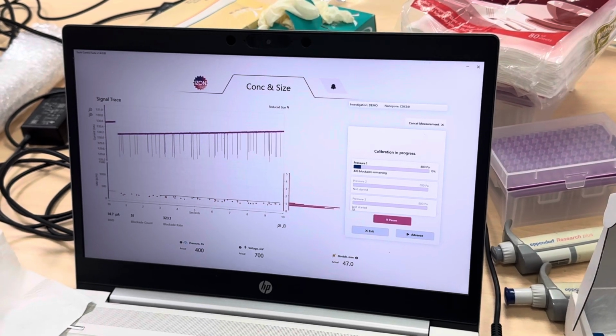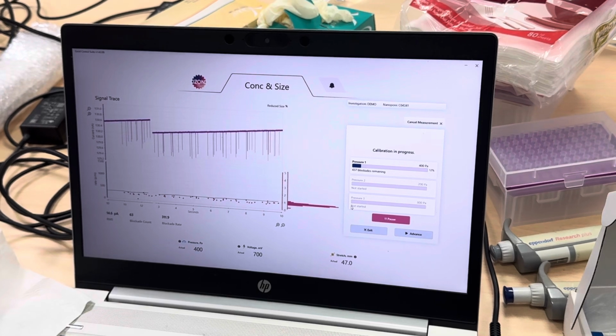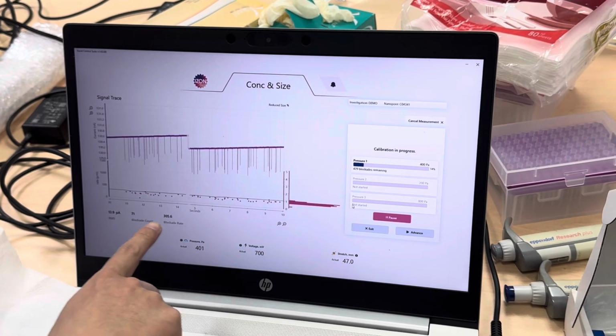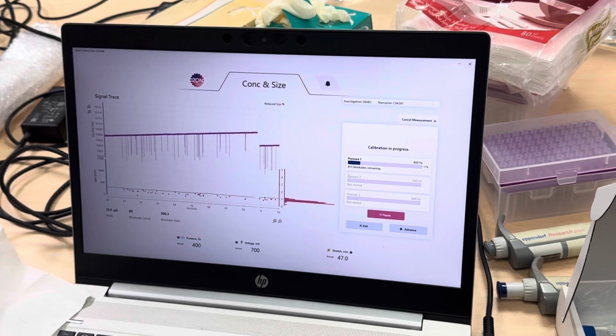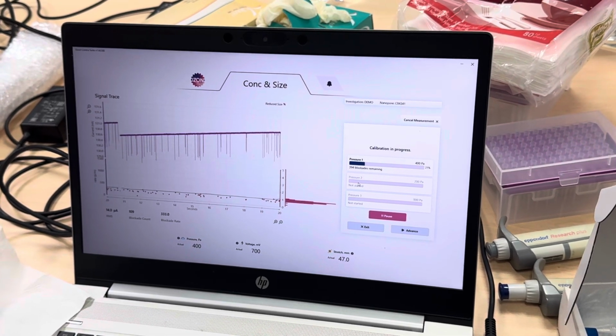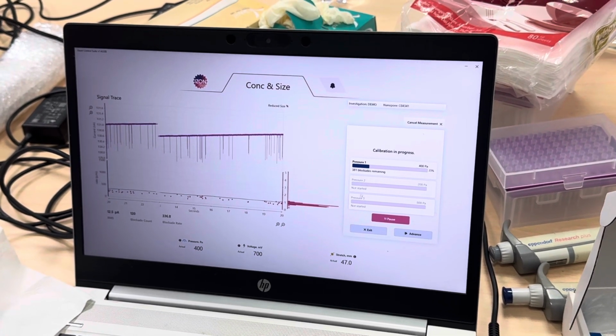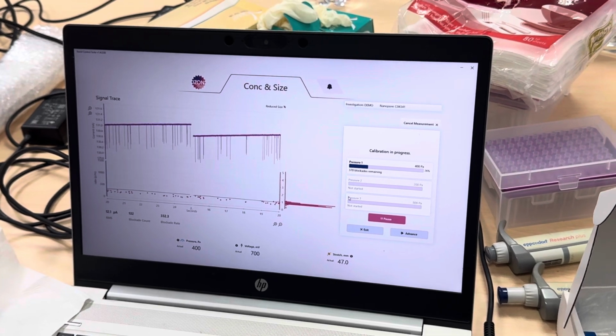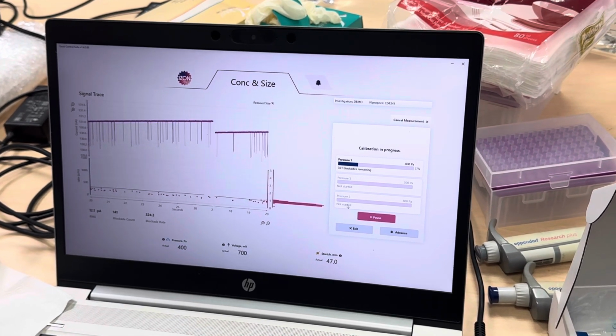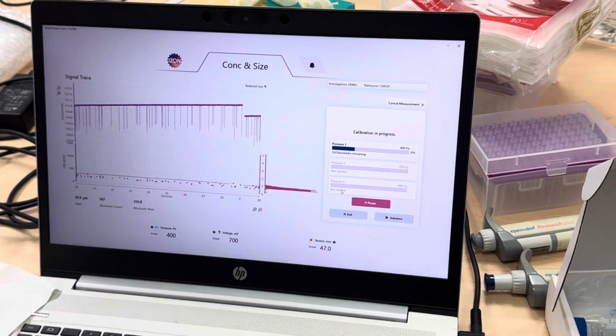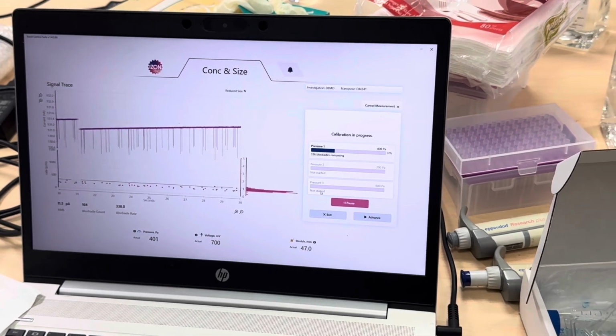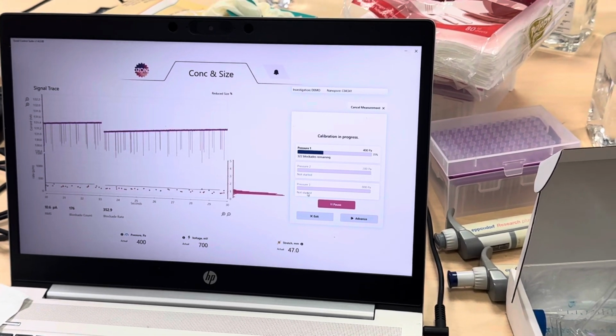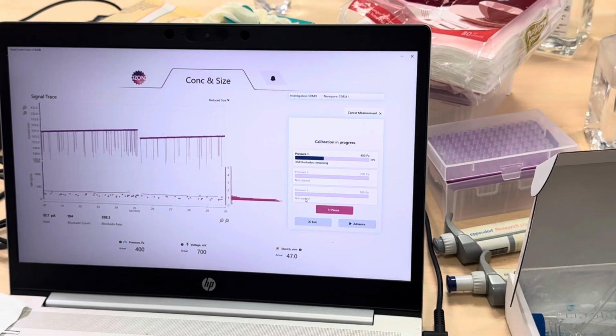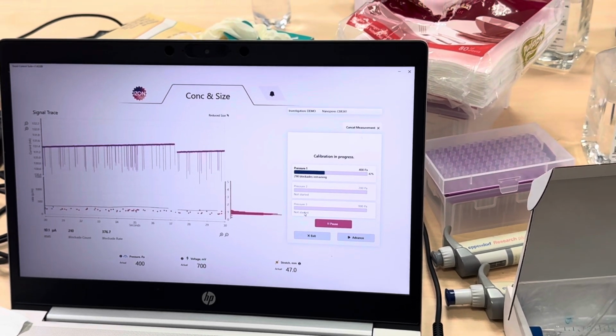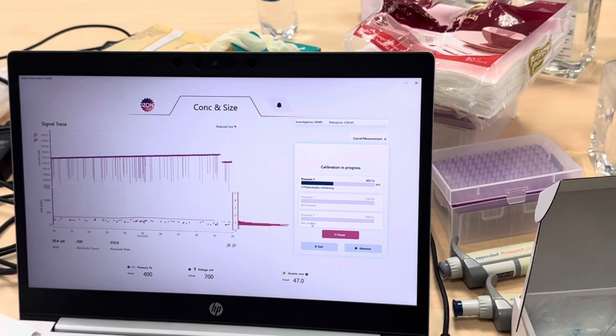How long until it's finished? For the calibration, you can see the particle rate, it should take around 5 minutes for the calibration particles, because we said that usually three-pressure calibration is the most accurate. Usually for a quick screen you can just use 2 pressures, because the three pressures are to make sure it forms a linear relationship. Yeah. Basically, 2 pressures is already linear. 3 pressures is to make sure the third point falls into the linear one. Yeah.